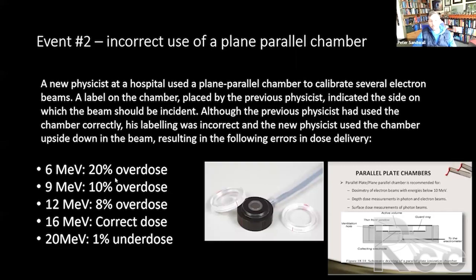For 6 MeV, it was a 20% overdose because it expected a higher reading, so he turned it up. 9 MeV, a 10% overdose. 12 MeV, 8% overdose. 16 MeV happened to be in the sweet spot, so it wasn't that big of a deal. And same with 20 MeV, 1% underdose. And that 1% you might even call noise. But these other ones are quite significant.